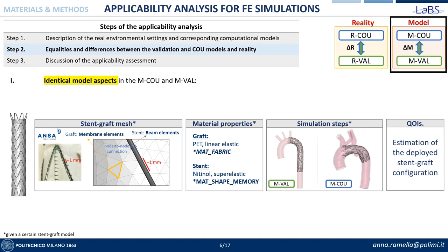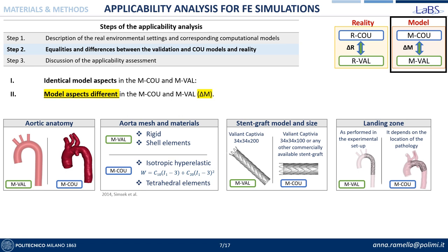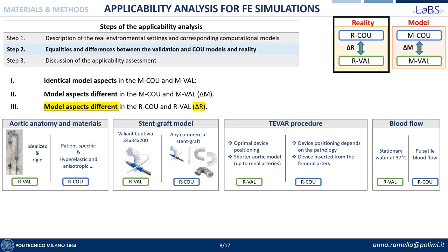The second step consists of describing the equalities and differences between the reality and the models. The identical aspects on the model side are related to the stent graft discretization technique and material properties, the steps of the simulations, and the quantities of interest. While on the other side, differences are related to the aortic anatomy, to the kind of material and discretization technique of the aorta, to the stent graft size, and to the landing zone of the implanted stent graft. Switching from the model to the real environmental settings, differences are related to the aortic anatomy and materials, to the stent graft model, to the TEVAR procedure itself, and to the presence or absence of blood flow.